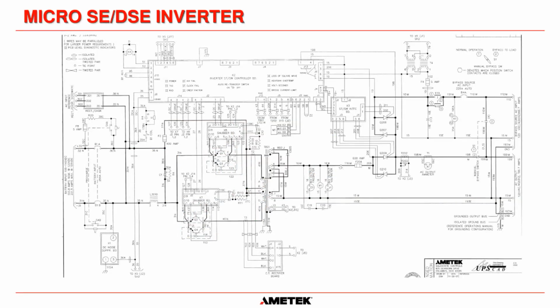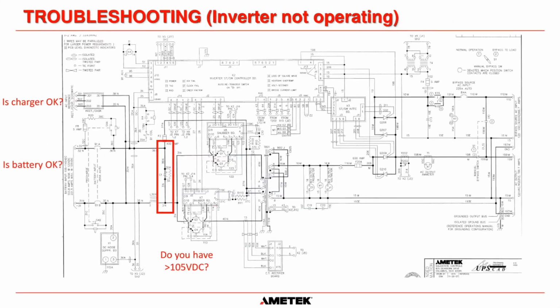And then if you measured across that primary of the transformer, you would measure the square wave, and on the secondary of the ferroresonant transformer, you would see a relatively nice AC waveform because of the capacitor and the inductors inside the transformer, inside the ferroresonant transformer. That smooths out the square wave into a nice sinusoidal AC waveform. Okay, so that's the basics of how a micro-ferro UPS works.